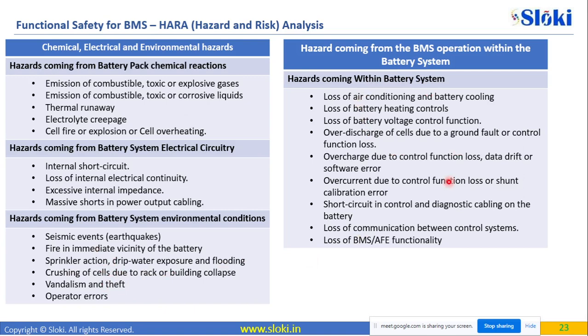Hazards coming within the battery systems include loss of air conditioning or cooling effect, and possible ways that can lead to a BMS failure: loss of battery heating controls, loss of battery voltage control functions, over-discharge, over-charging, over-current, short circuit in the diagnostic cabling, loss of communication with the vehicle control unit, and problems with the microcontroller or analog front-end chips.